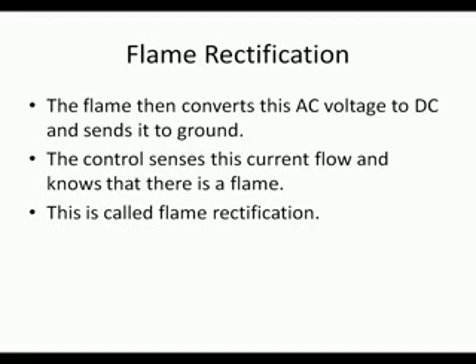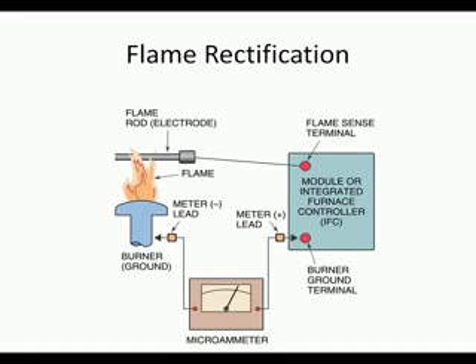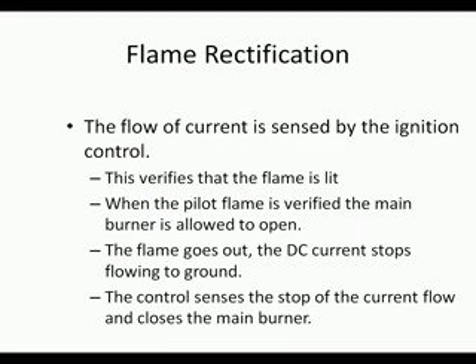What happens is once the ignition process starts, the spark or hot surface igniter ignites the flame. Once the flame is ignited, the flame is a conductor. A very little AC voltage is sent through the flame sensor rod. The flame then converts this AC voltage and current to DC and sends it to ground. The control senses this flow of current and knows that there's a flame present. This is called flame rectification because rectification is the change of AC voltage to DC.